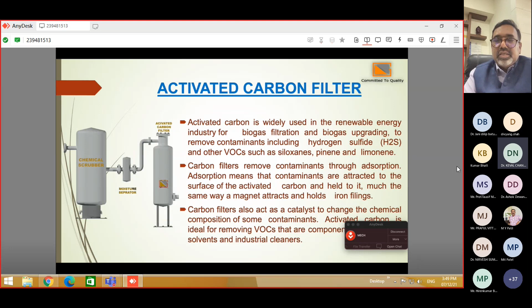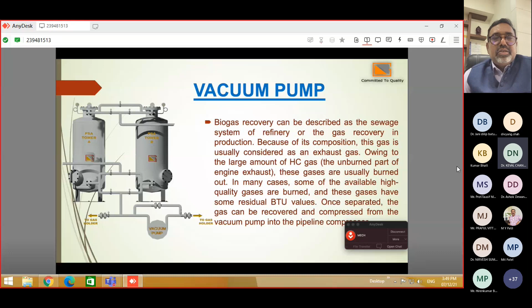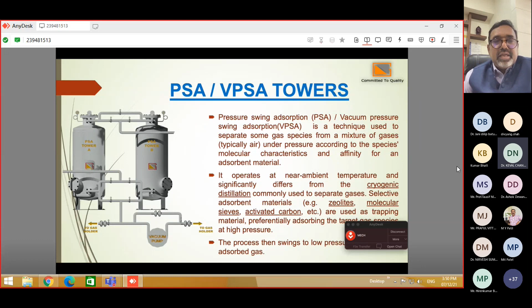Then we have the PSA system, where regeneration is done through a vacuum pump. These are the PSA towers, where zeolite molecular sieves are filled into both the towers, and they are adsorbing the CO2 and other gases to produce enriched methane, which is equivalent to or better than CNG. This is the surge vessel where the pure gas is collected and analyzed.